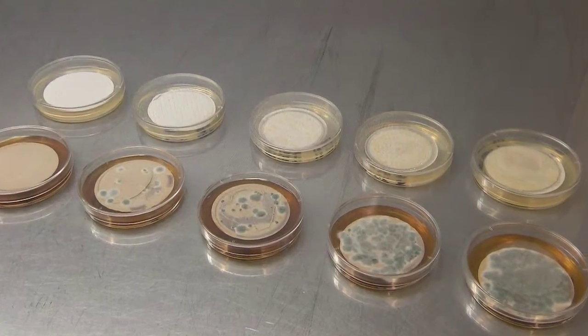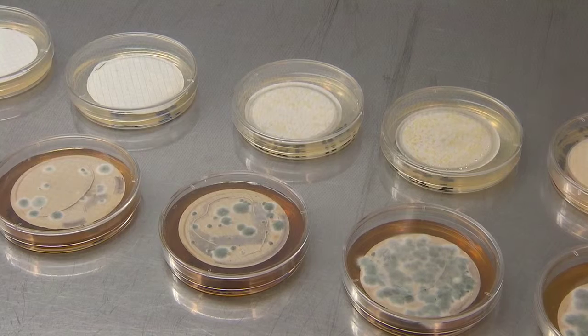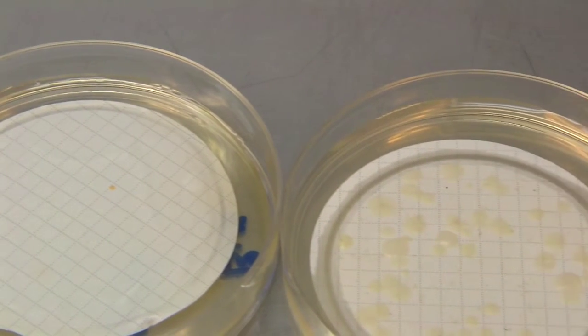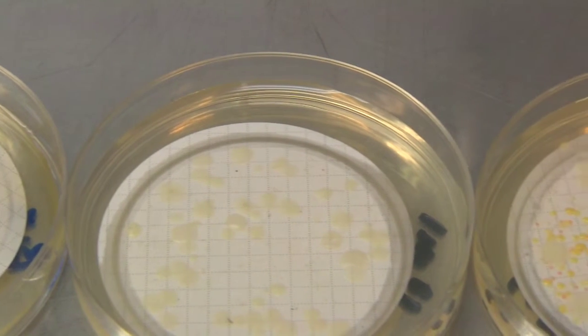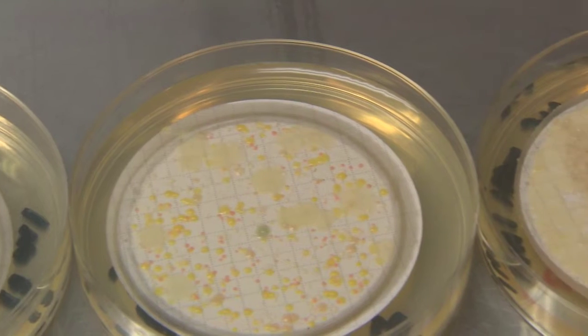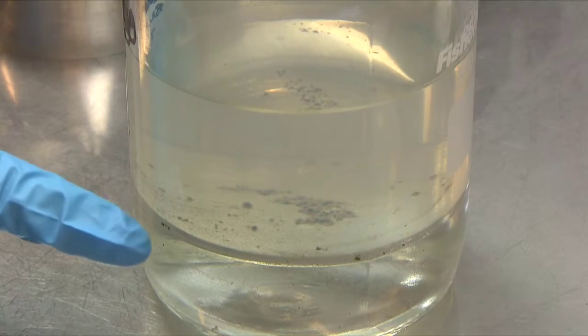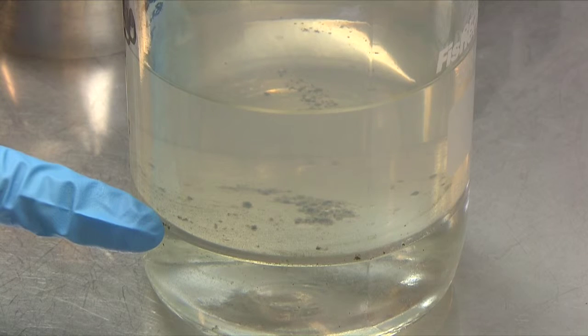Microorganisms, or bugs as they are commonly called, are living organisms that are too small to be seen by the naked eye. They are usually single-celled organisms such as bacteria, yeasts, mold, fungi or algae. Bugs require water for growth, and although bacteria and fungi can be present in the fuel phase, their growth and activity is generally restricted to the water phase of the fuel.